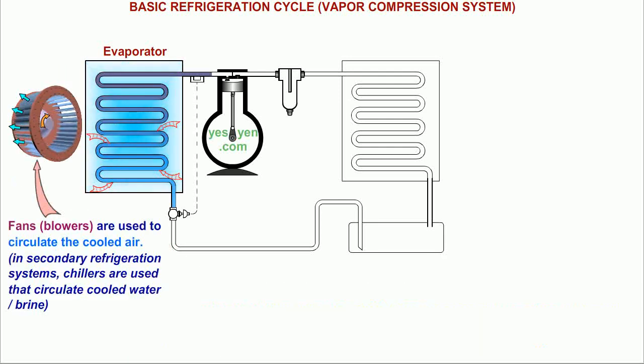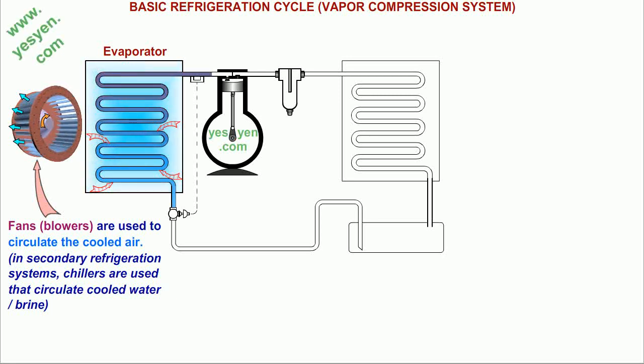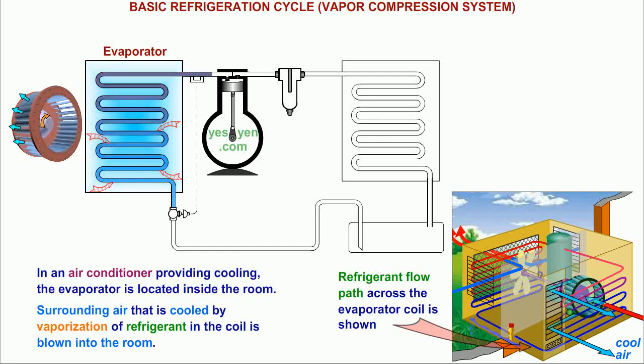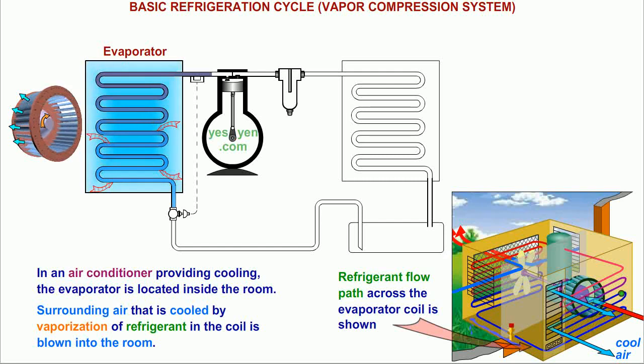thus cooling the surroundings. Fans are used to circulate the cooled air. In secondary refrigeration systems, chillers are used that circulate cooled water or brine. In an air conditioner providing cooling, the evaporator is located inside the room. Surrounding air that is cooled by vaporization of refrigerant in the coil is blown into the room. Refrigerant flow path across the evaporator coil is as shown.